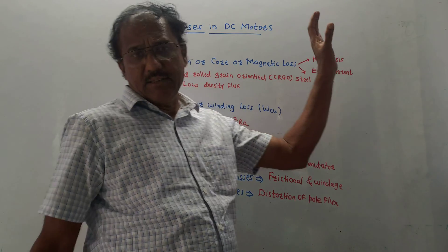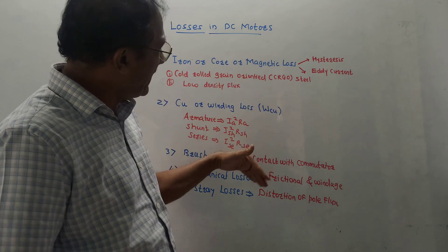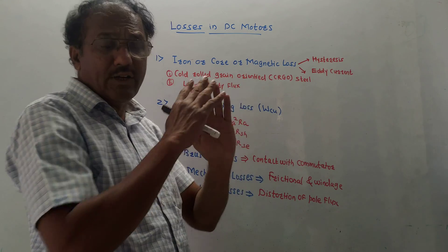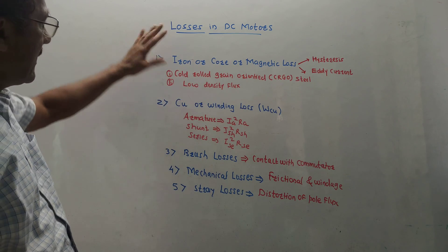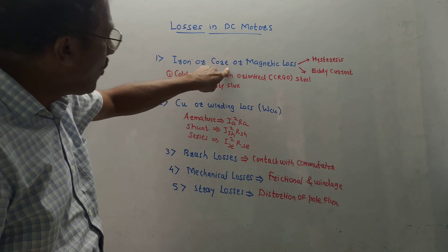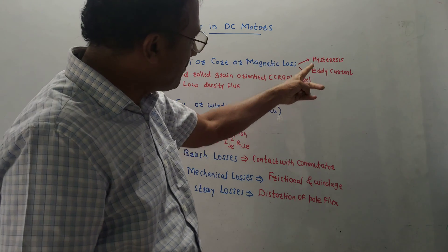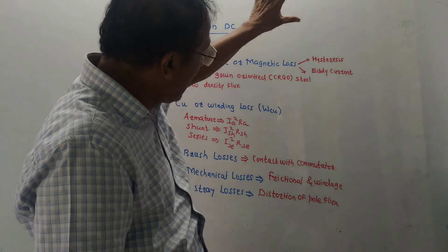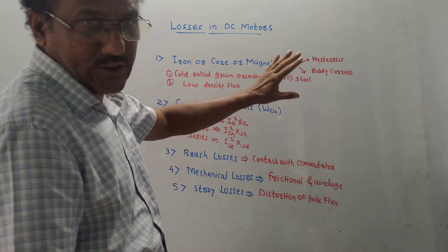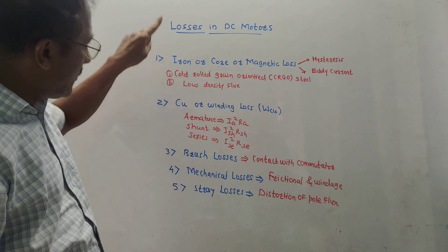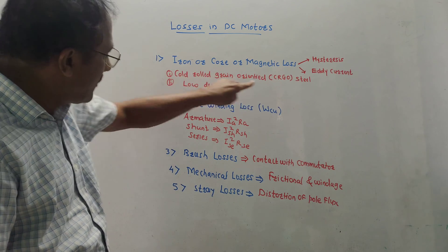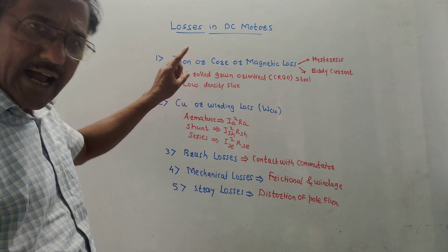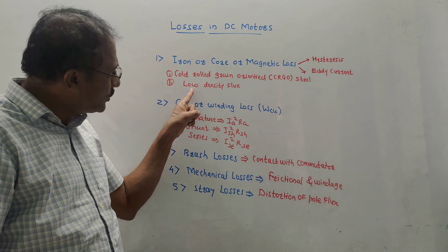Next part is losses in DC motors. First loss is iron or core or magnetic loss — remember two words: it is due to hysteresis loss and eddy current loss. These losses are fixed losses. To minimize these losses: use CRGO (cold rolled grain oriented) steel material, and use low density flux.